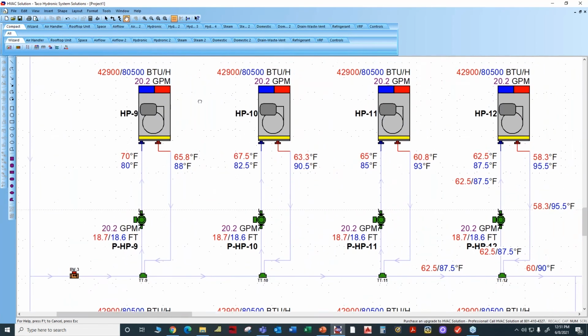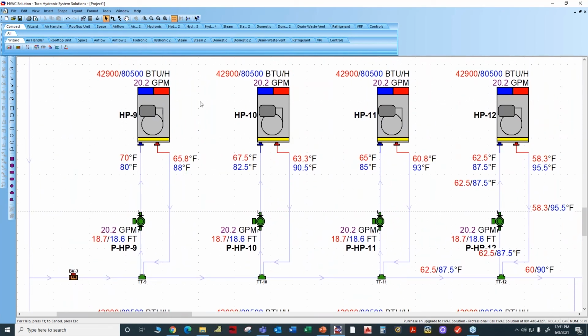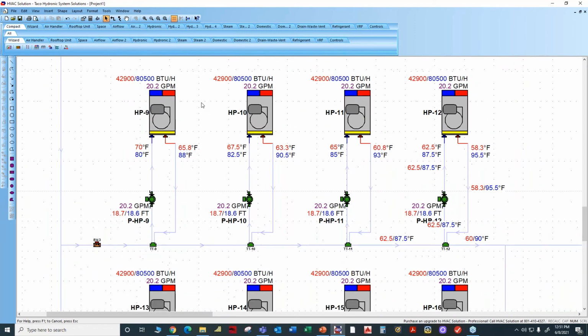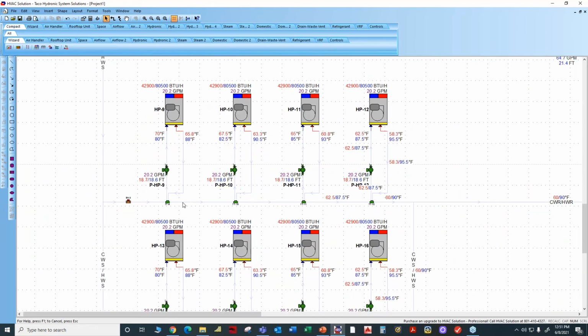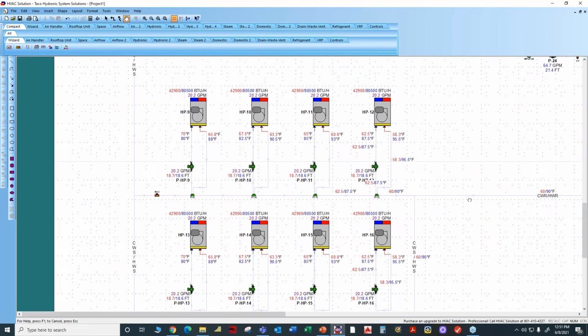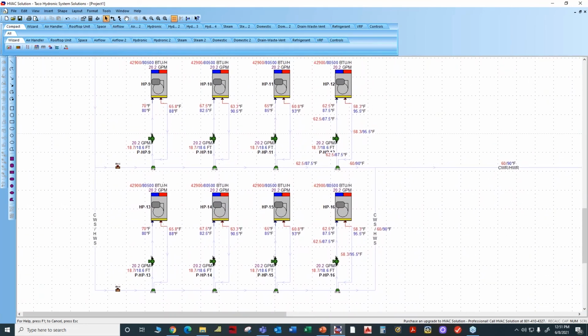And so we can save on pumping energy, and we can also save on piping because instead of having a supply and return pipe on each floor, we only have one pipe. So we call this our load match system. Generically, it's known as a single pipe system. So that's why we're using circulators.